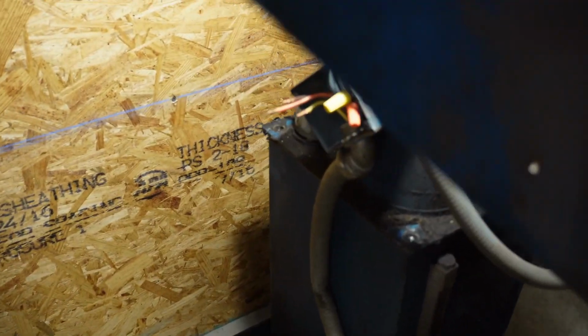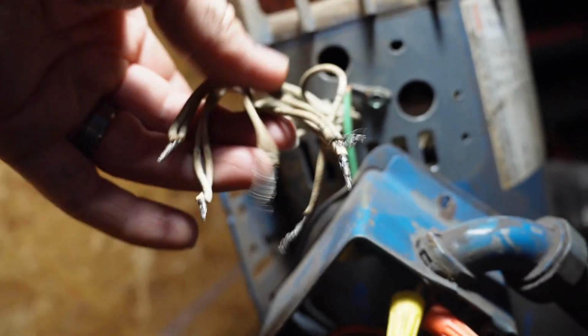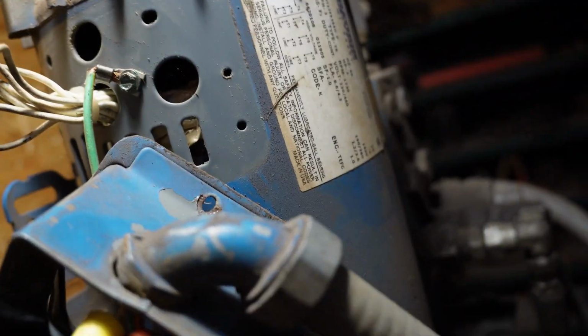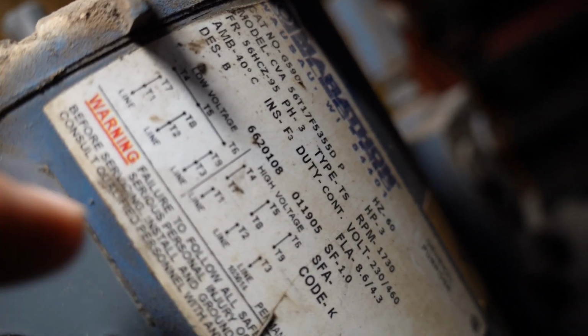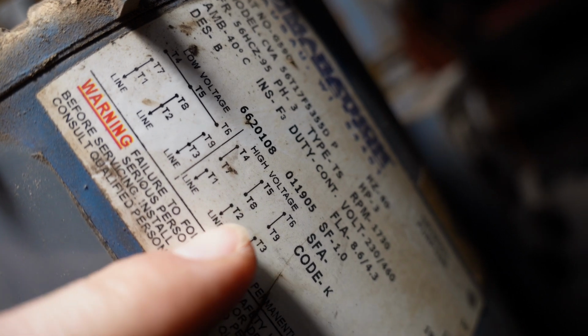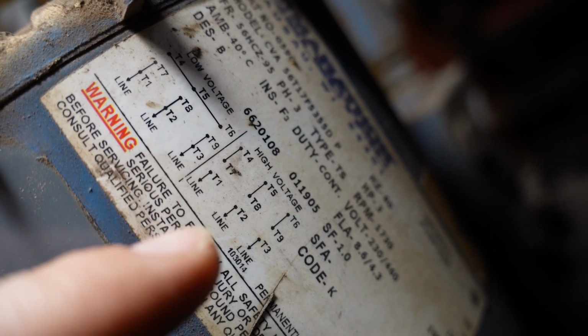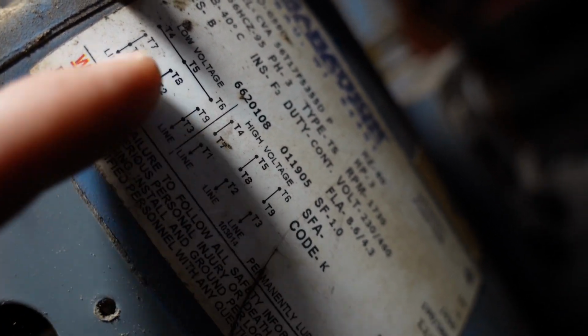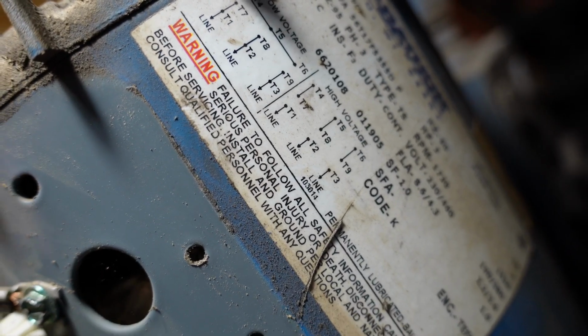Now this next step is crucial. I've already disconnected all my leads to the windings, because if you look here, hopefully the camera can get this, it shows low voltage and high voltage wiring diagrams. This was set up for high voltage. Now we're going to swap it over to the low voltage winding configuration.